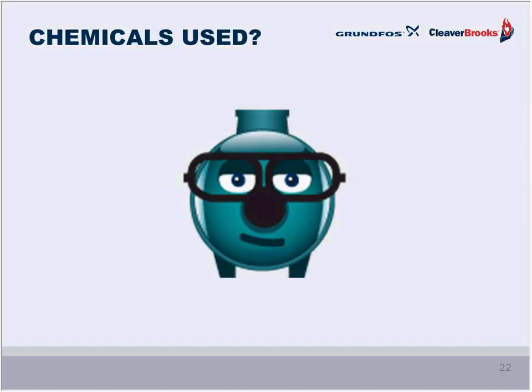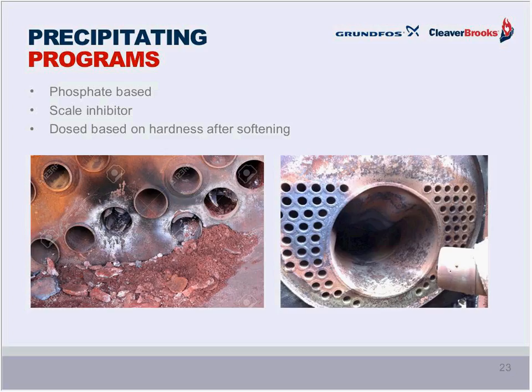And, well, that's all well and good about the levels of impurities that can be tolerated in the boiler, but what chemicals are used to limit these impurities, thereby augmenting the mechanical removal devices? The answer is we often encounter a phosphate treatment used to supplement softening, especially when the water is very hard. And this is a treatment strategy which has been around for a very long time, and though effective, it can increase continuous blowdown rates and thereby waste water and energy.